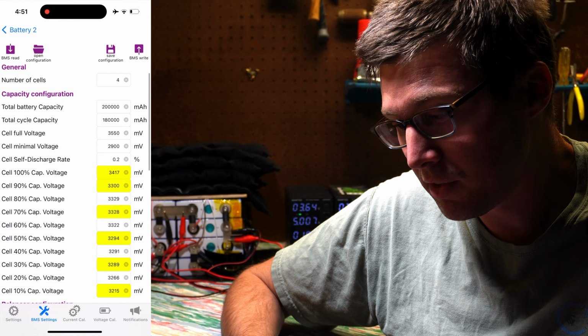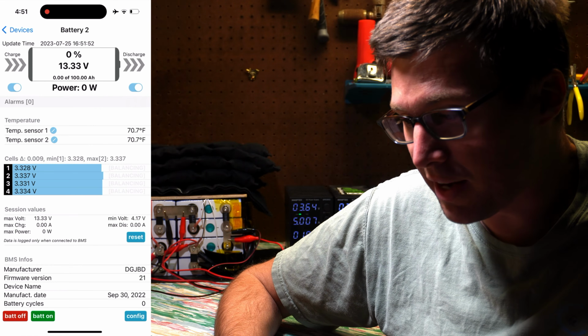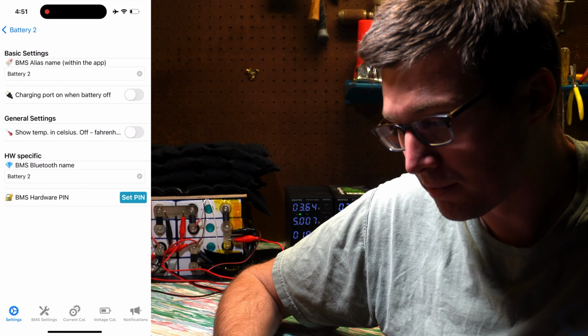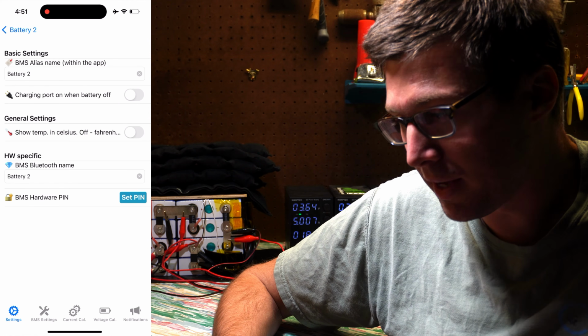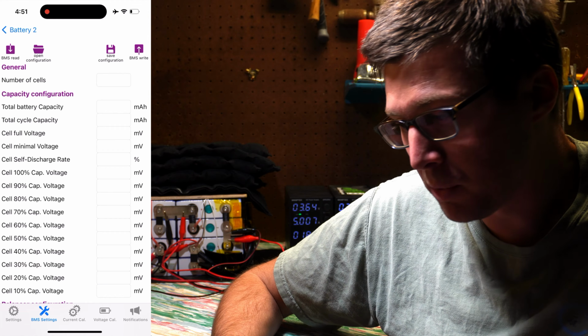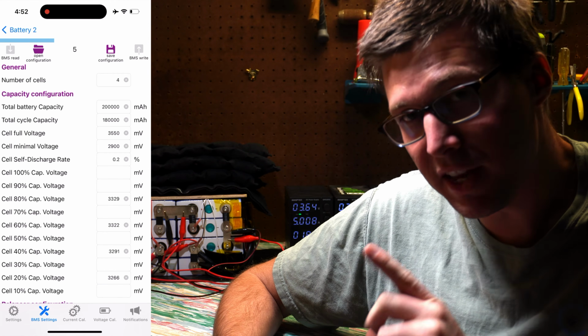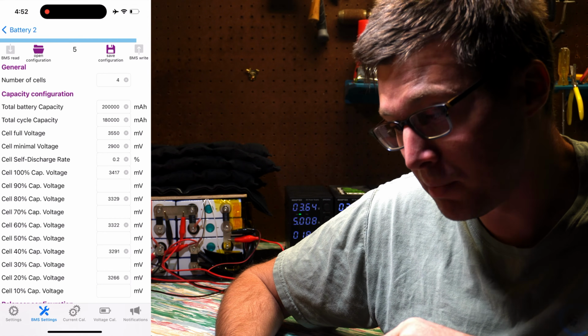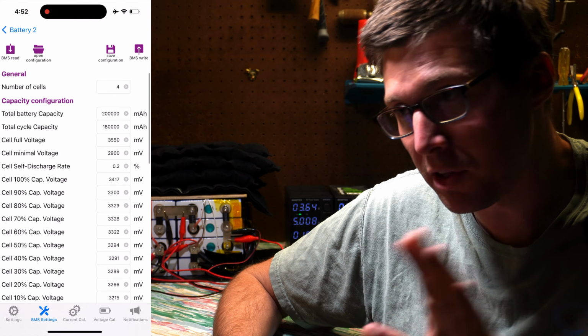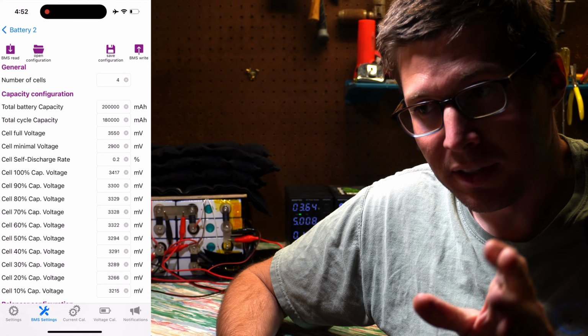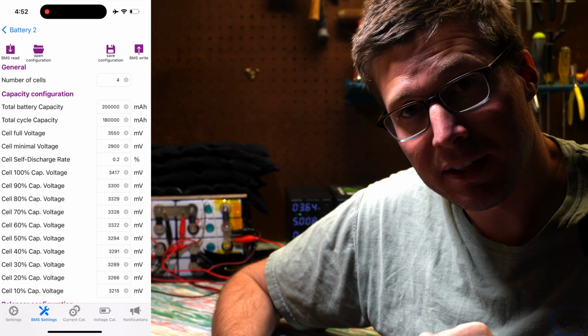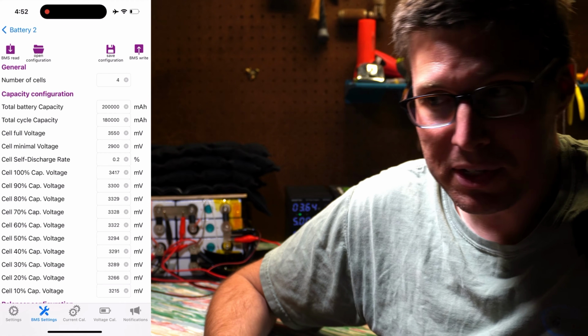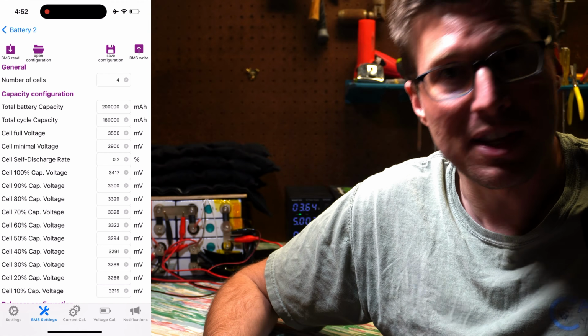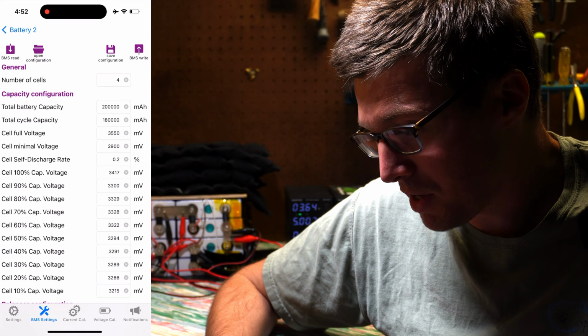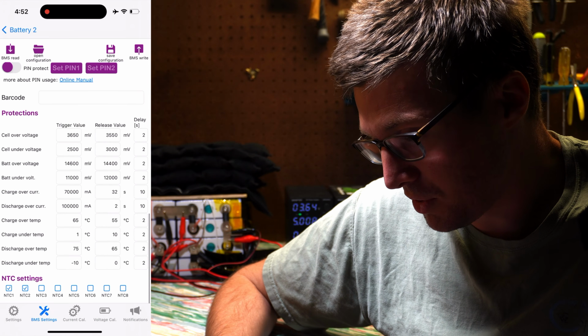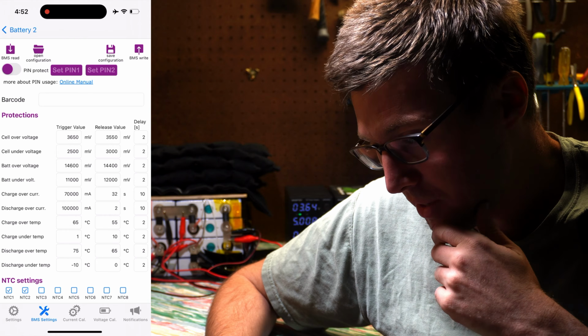So then we leave, but I like to go back in, open it again, and do a BMS read to make sure the settings I entered actually got saved, because I've had it happen before where I set all the parameters, left, and nothing updated. Then when I was using the batteries they weren't working right because they weren't set properly. So just come back in here, confirm everything's good, and we're set.